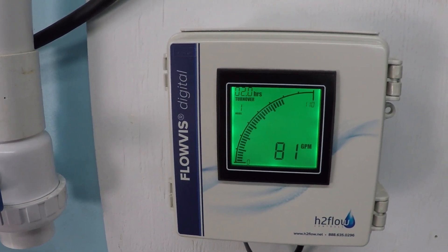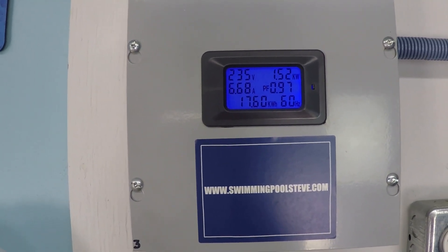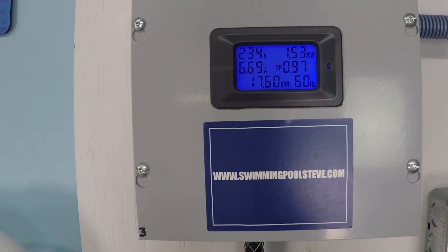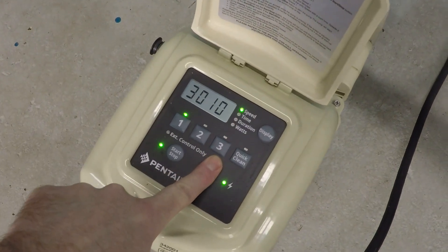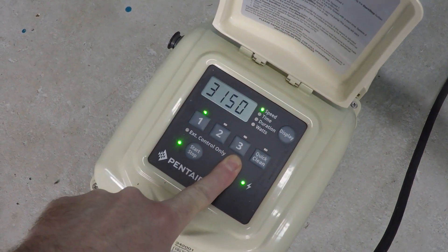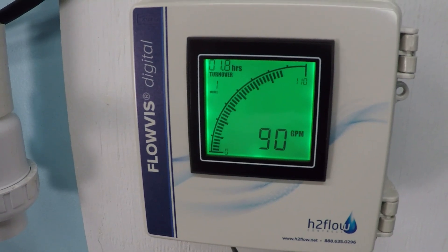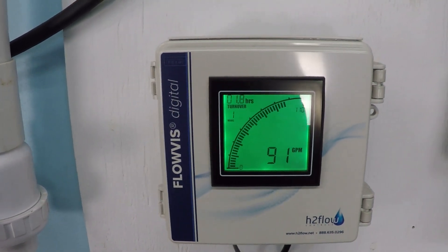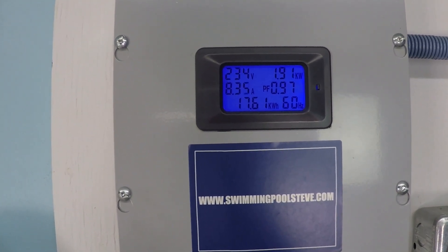So that's the limit at that setting — between 81 and 82 gallons per minute at 1.53 kilowatts, that's 1,530 watts. Stepping up further, we're just over 90 to 91 gallons per minute at 1.91 kilowatts, which is 1,910 watts.